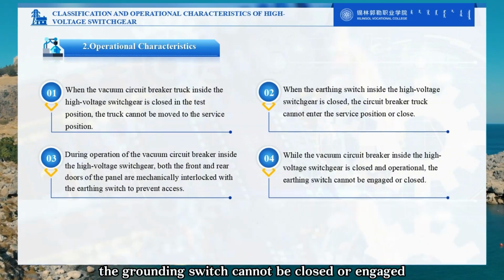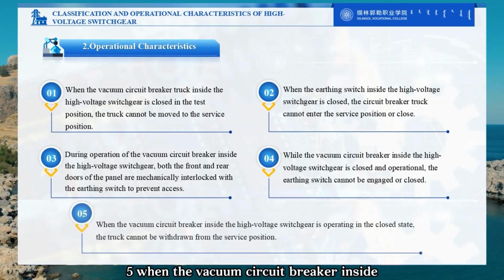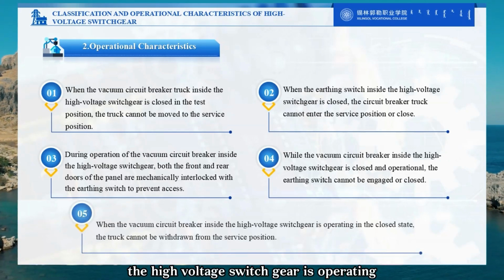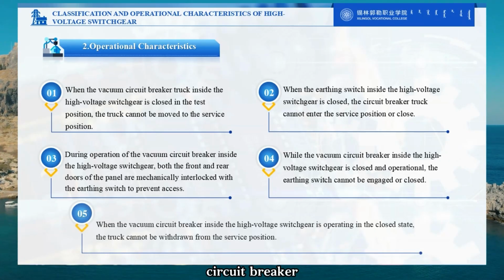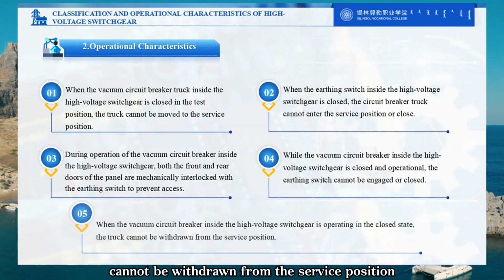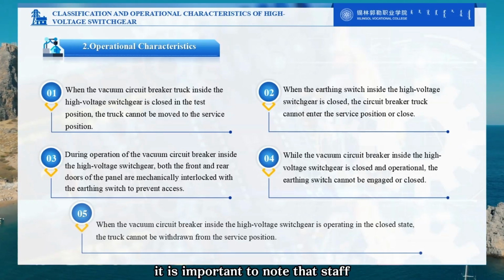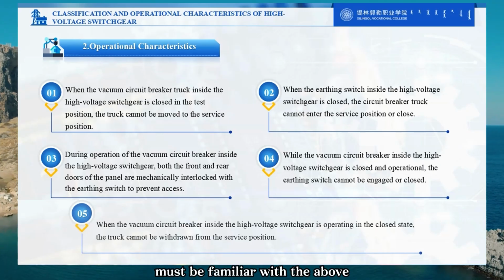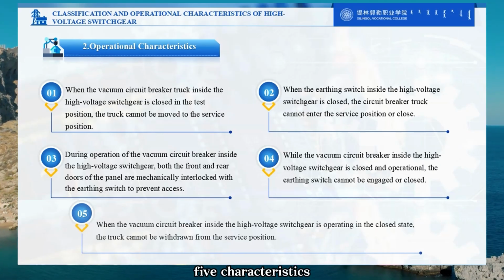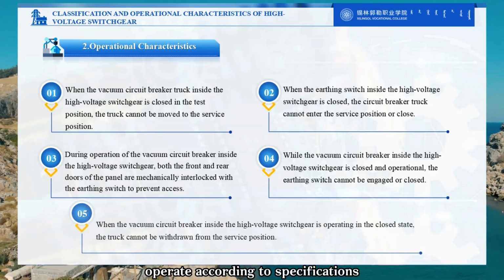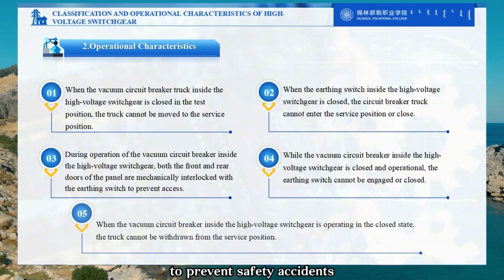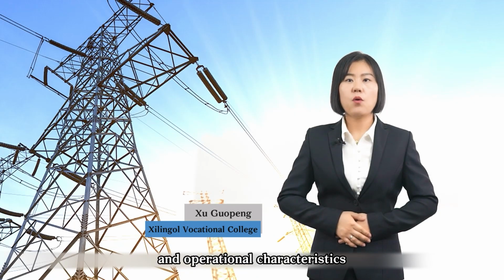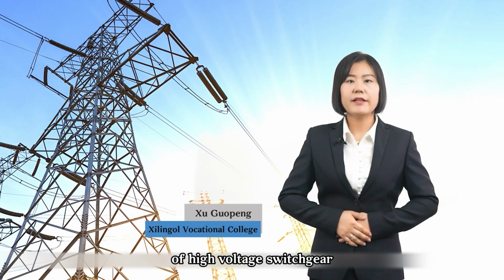4. When the vacuum circuit breaker inside the high-voltage switchgear is operating and closed, the grounding switch cannot be closed or engaged. 5. When the vacuum circuit breaker inside the high-voltage switchgear is operating and closed, the truck circuit breaker cannot be withdrawn from the service position. It is important to note that staff operating high-voltage switchgear must be familiar with the above 5 characteristics. Operate according to specifications to prevent safety accidents. The above is about the main structure and operational characteristics of high-voltage switchgear.